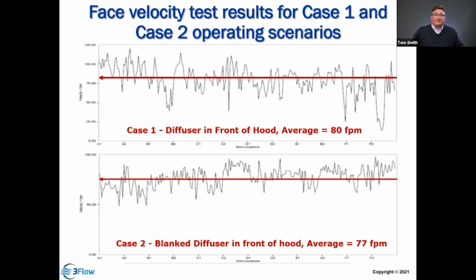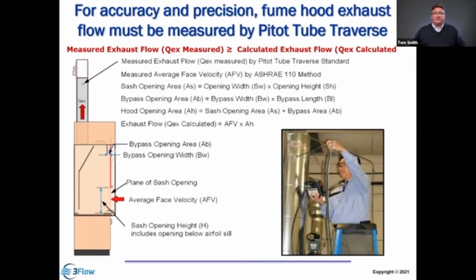Now, looking at the impact of those cross-drafts, we can see in case 1, there's a lot of variation here. We had velocities less than 20 feet per minute in some cases because of the impact of those cross-drafts on the opening, and you can see how hard it would be for the hood to contain under those conditions. In case 2, where we're blanking off the diffuser, it's more stable, and so the hood has a better probability of providing adequate containment. And it means that the velocity is more consistent. So we want to eliminate the cross-drafts and get the right average. Now, oftentimes the hood test that's occurring now in the lab is compared to the measures that were done by the pitot tube traverse in the exhaust duct.